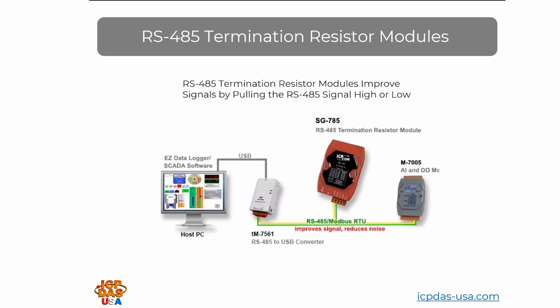Our RS-485 termination resistor modules help pull the RS-485 signal high or low. Different manufacturers have different RS-485 products, and for the most part, they all can communicate with each other, but this particular product is going to help improve that signal if you should have any kind of communication issue.